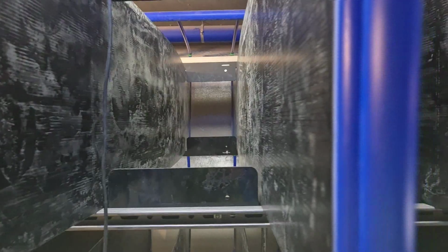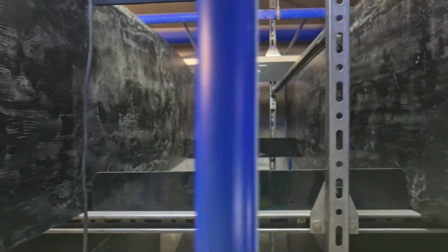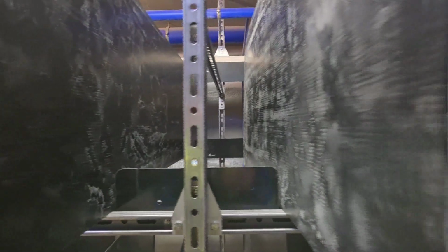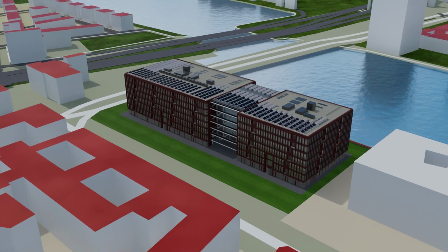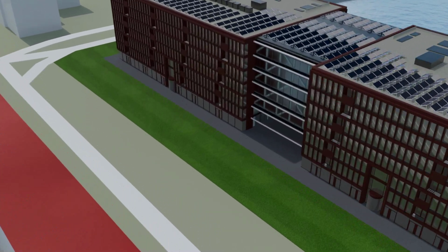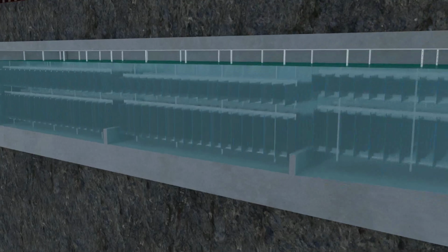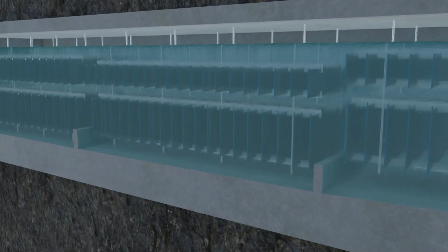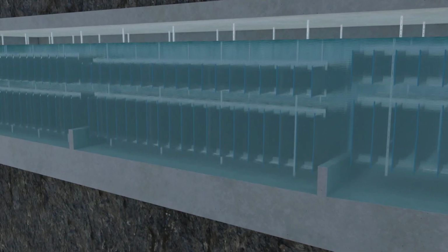The plate heat exchangers extract the last bit of heat from the 0-degree cold water, and it freezes. During this change of state from liquid to solid, the same amount of heat can still be extracted from the water as when the water is being cooled from 80 degrees to 0 degrees Celsius. This physical phenomenon is also put to use here in Berlin. This way, a large amount of additional heat can be extracted from the water. In February, the first ice particles form on the plates.